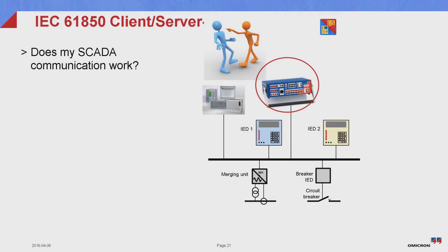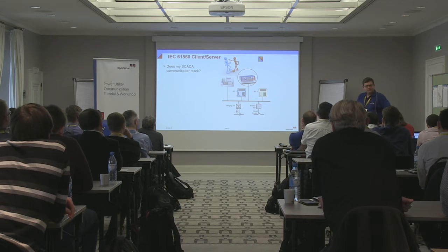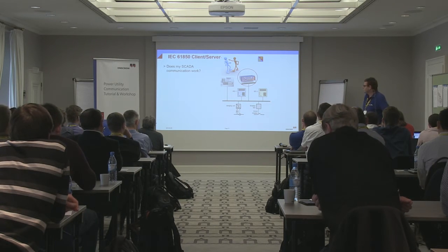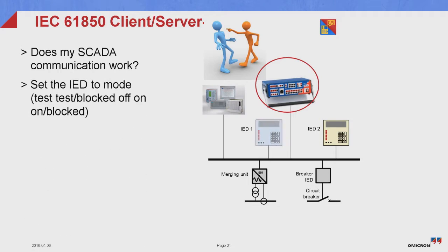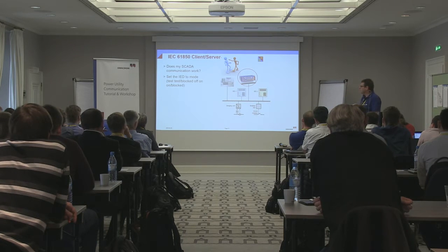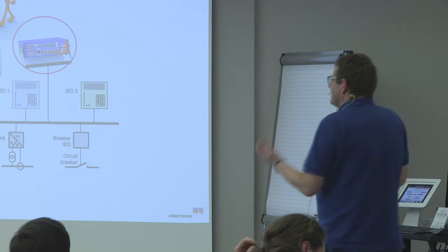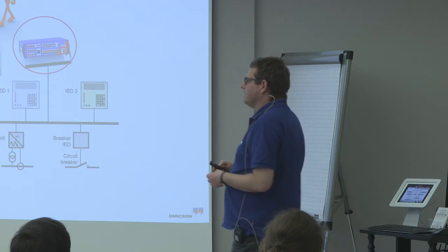And the idea is that you then have the possibility of what we call the "whom to blame" use case, that you can also say, okay, during protection testing I also check that the SCADA communication works properly. So I check this. And additionally, the main reason, I can set the IED or different functions to this test mode. So this should not be done just with additional software, this really should be done during protection testing. And that's why our proposal is to do it like this.